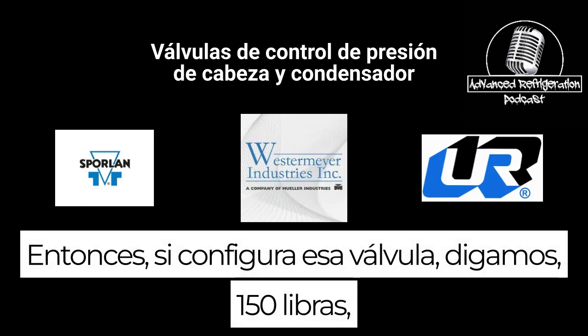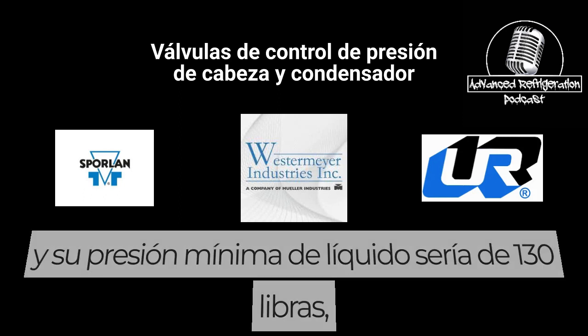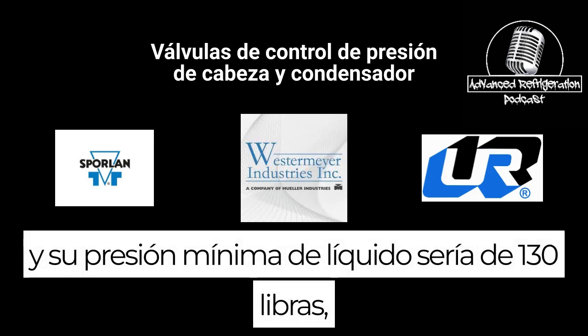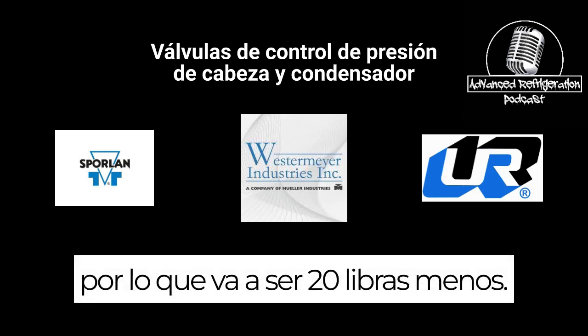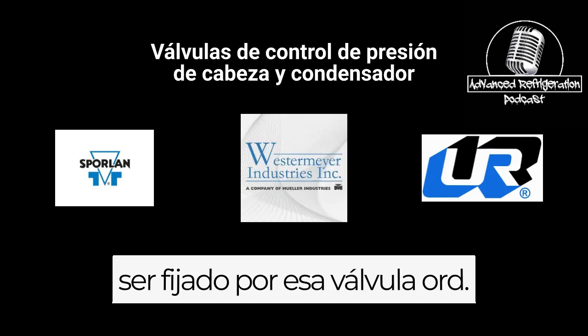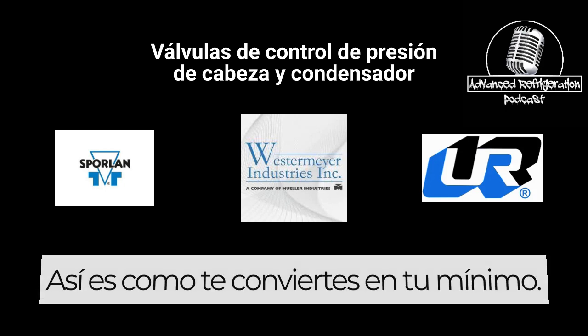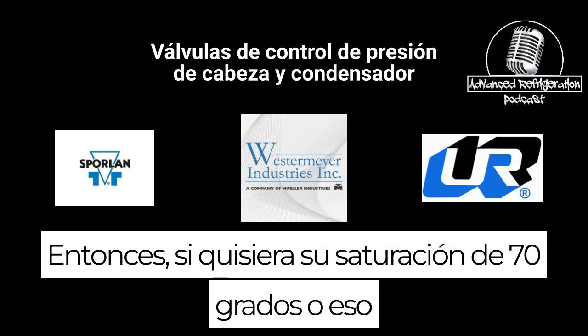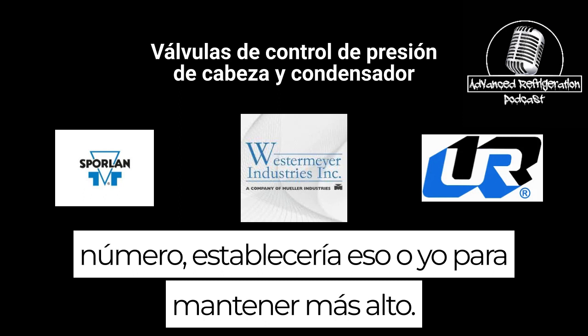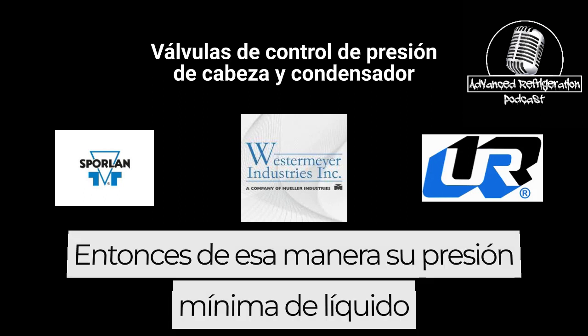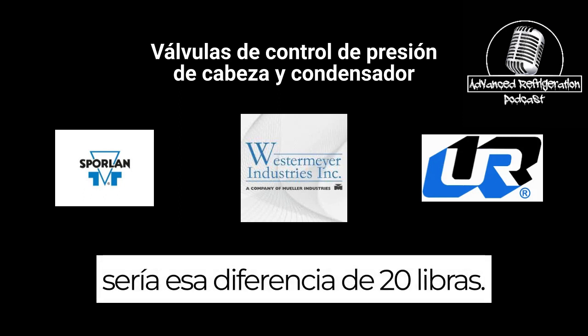So if you set that valve, say at 150 pounds, your minimum liquid pressure would be 130 pounds. So it's going to be 20 pounds less. Your minimum liquid pressure would be set by that ORD valve. So that's how you get your minimum. If you wanted your 70 degree saturation or that number, you would set that ORD to maintain higher, so that your minimum liquid pressure would be that 20 pound difference.